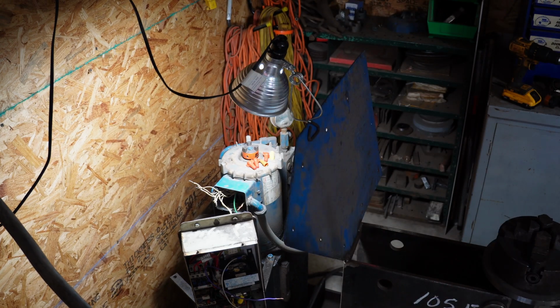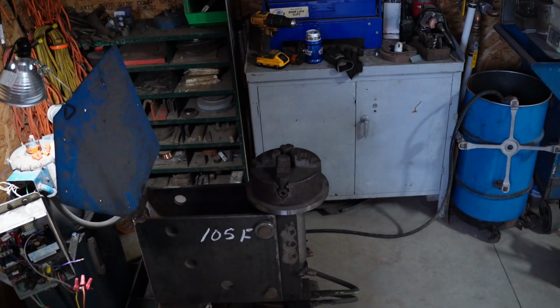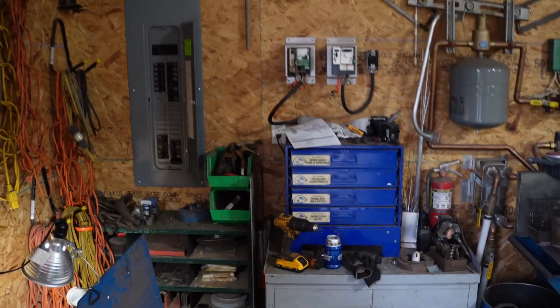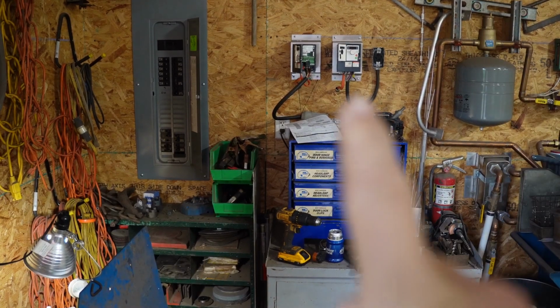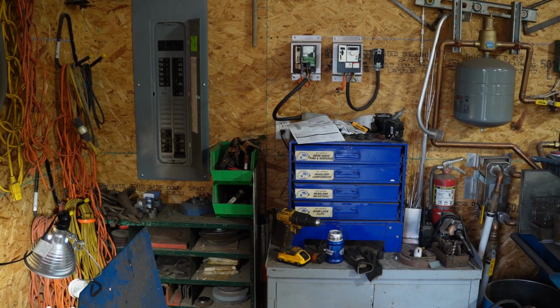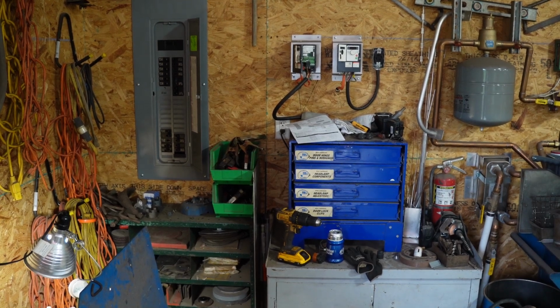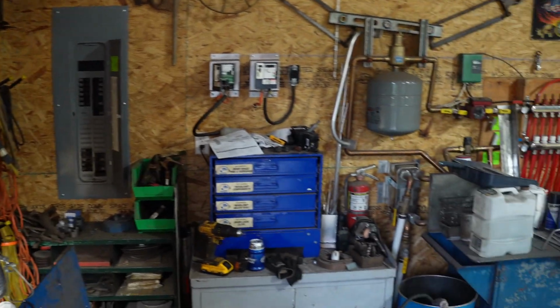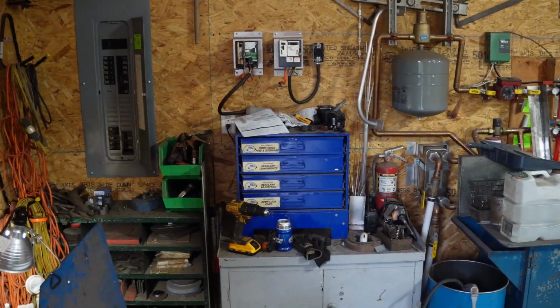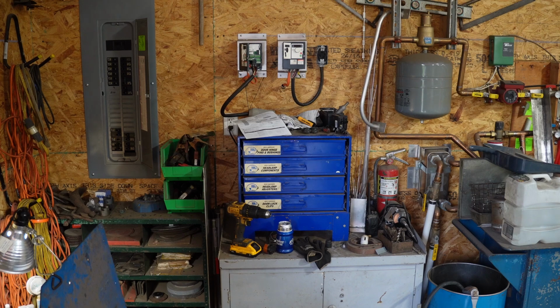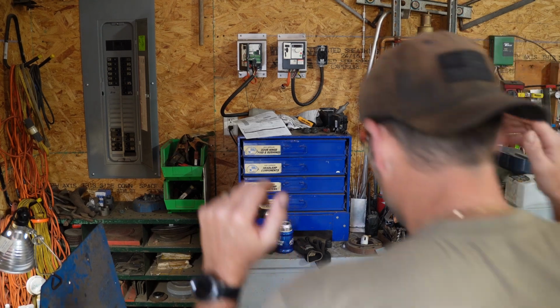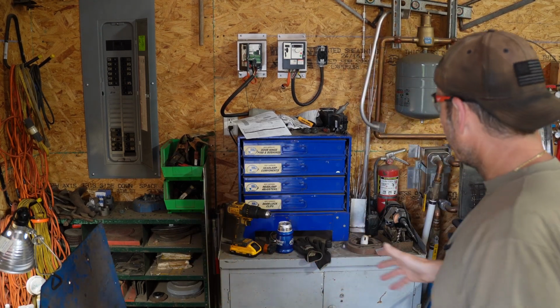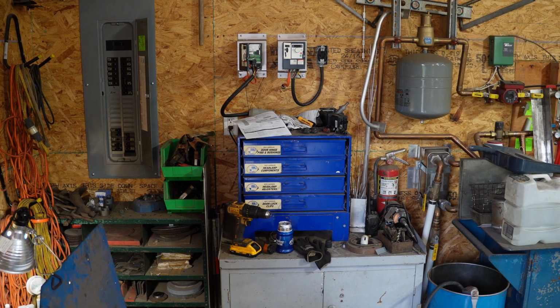So now I'm going to check all of my wiring from the actual VFD all the way back to the unit. Even though I don't think it matters, I'm going to make sure I got the proper wires coming from the VFD to the outlet, and from the outlet to the machine, making sure they're all in sync with each other, if that makes sense. So U1, V1, W1, line 1, line 2, line 3 - I want them all to be the same, even though I don't think it matters. That's what I'm going to check next.